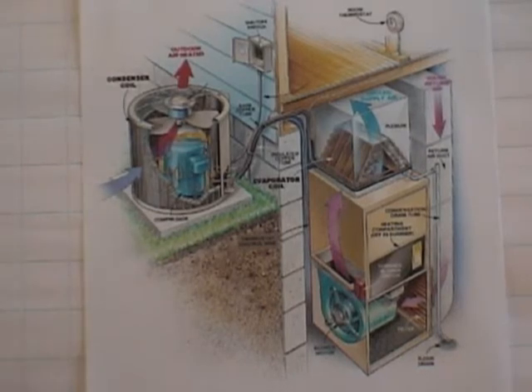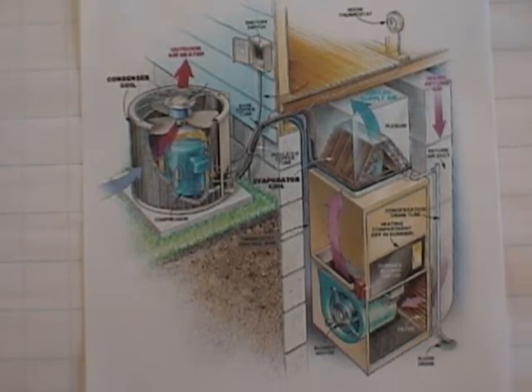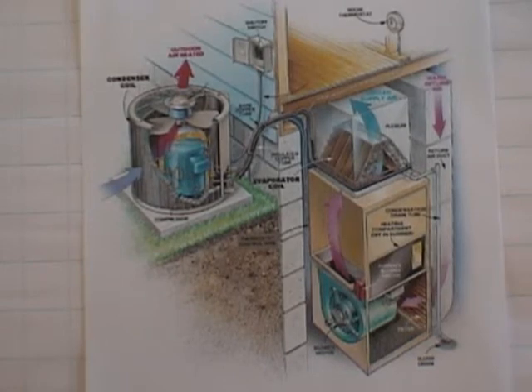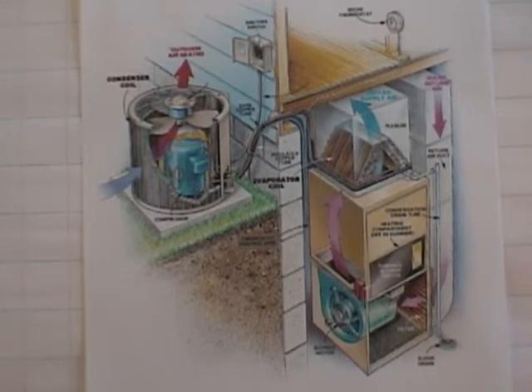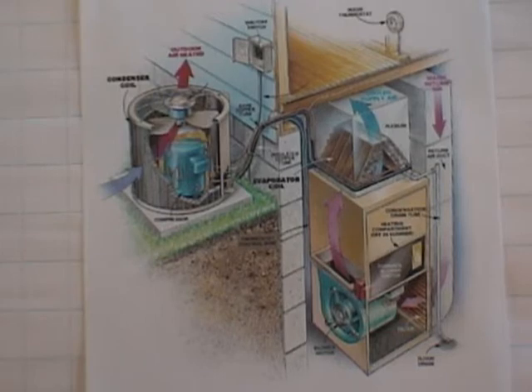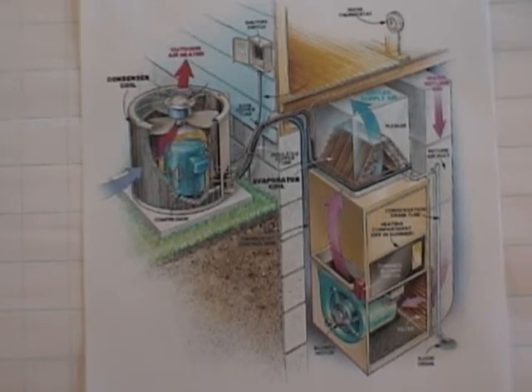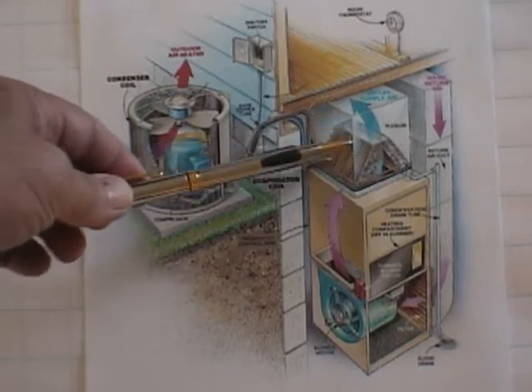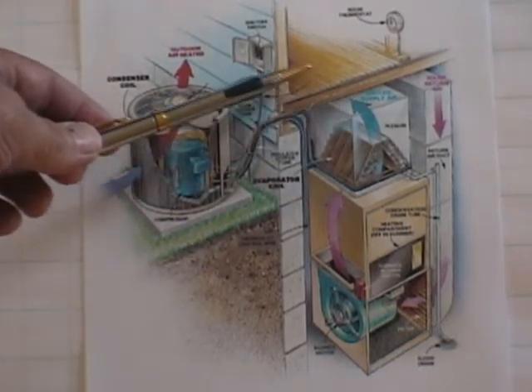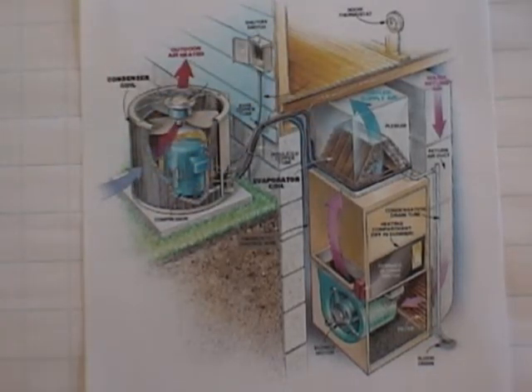In order to measure the total heat across the evaporator coil, we need to take a dry bulb and wet bulb temperature with our humidity stick in the return air or mixed air stream, and also in the supply air stream. We want to place the humidity stick in the supply air stream out of sight of the evaporator coil if possible, at least two feet away from the coil to get a good average temperature. Anywhere too close to the coil would not be a good location, so we need to get downstream and preferably out of sight.